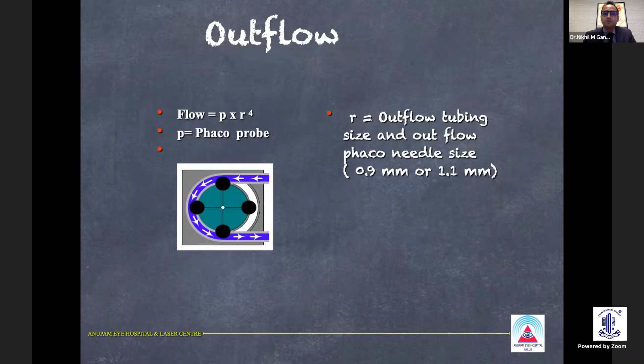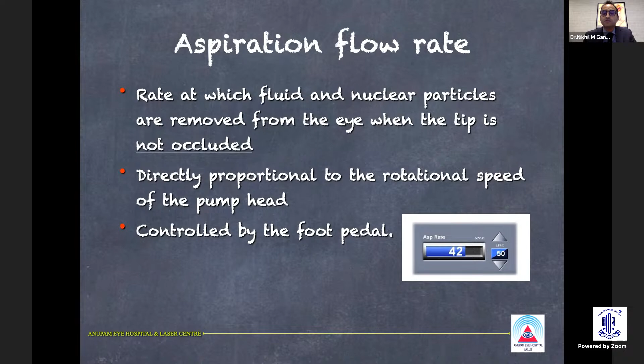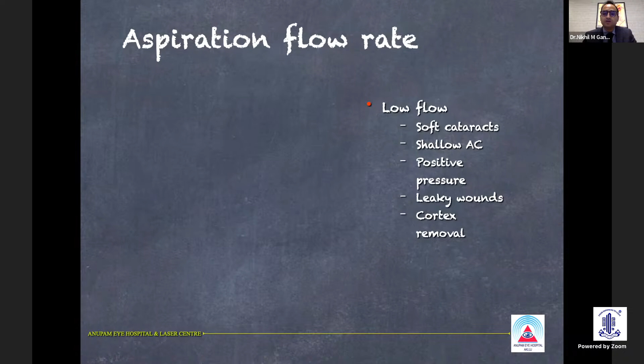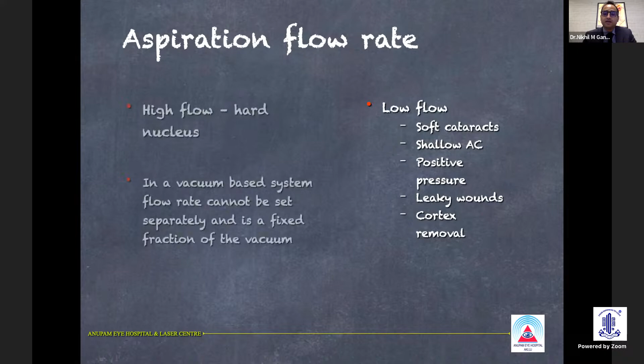So aspiration flow rate is the rate at which the fluid and nuclear particles are removed from the eye when the tip is not occluded. And this is directly proportional to the rotational speed of the pump head, which is controlled by the foot pedal. So when should a low flow rate be maintained? When you see soft cataracts, shallow ACs, positive pressure patients, leaky wounds, and in cortex removals. And high flow rate should be kept during the hard nucleuses.